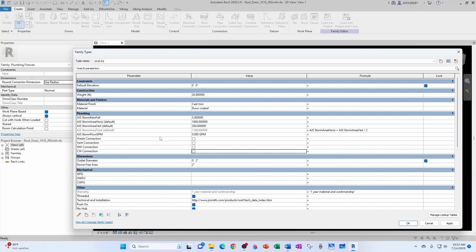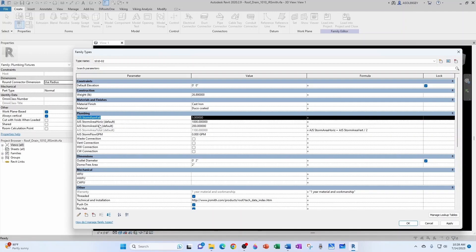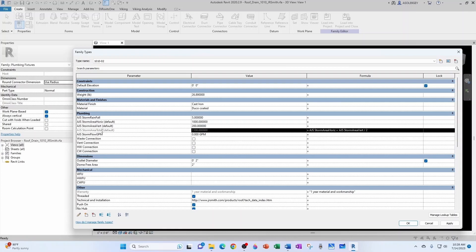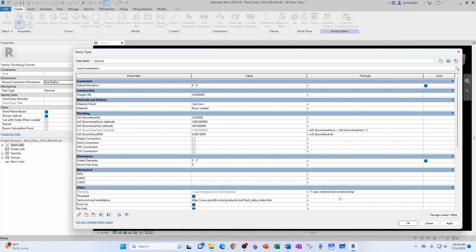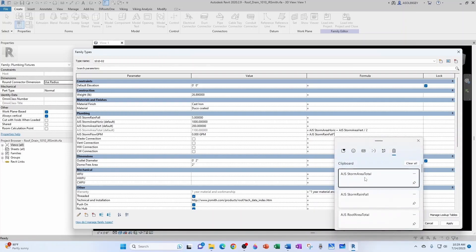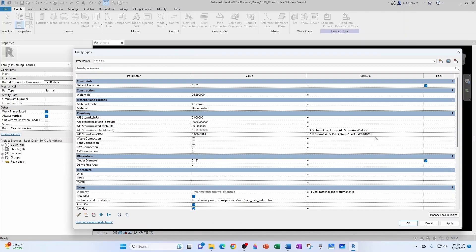Now the Storm Flow. So my Storm Drainage Flow is going to be the Rainfall times the Area. So my Rainfall, let me copy it over to my clipboard. And my Total Area, copy it to my clipboard. And now Windows V, so Rainfall, times my Total Area, Windows V, multiplied by a certain conversion factor, right? Because this Rainfall is in inches per hour, and this Total Area is in square feet. So if I want to have this in GPM, I would have to multiply that by 0.0104. And then this is still just a number, because this parameter is a number, this parameter is a number, and this is just a number. So I'm going to multiply that by 1 GPM. And that's giving me my 57.2 GPM. So, so far, so good.